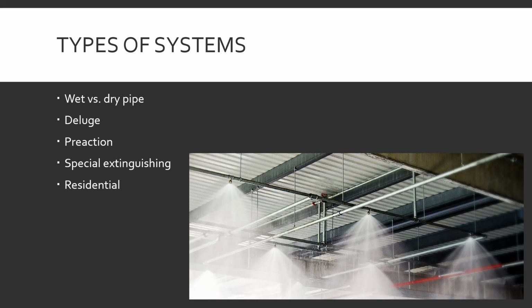Guy on the forklift hits it with the forklift. It's fun to pick on the forklift guy because it happens quite a bit. Hits it, and then there's water instantly. Sprinkler head comes off. There's water right there. Water's all over the floor. It's a wet pipe. Those are susceptible to getting a lot of sediment in there if the water just sits up there. That's why when you see a sprinkler head open, it's the dirtiest water you've ever seen coming out of them. Because that water may have been up there since 2008 or 2000, whenever they put the system in, and it hasn't been activated.